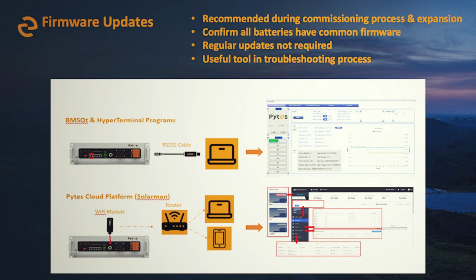The only other thing I'll leave with is updating firmware for the batteries. With all of our products, for me, it's an if it ain't broke, don't fix it mentality, so I really stand behind that. I will say, if you're doing a new system and you're commissioning that system, go ahead and update the firmware on the batteries. It's a good time to do it. Or if you've got a site that's been running for like 6 months flawlessly, no problems at all, and all of a sudden the customer calls and says, hey, this shut down, I'm getting an alarm, the batteries have blinky red lights and they're beeping. For me, if we didn't change anything with inverter settings, if we didn't change anything installation-wise, firmware is usually going to be the first thing I'm looking at there.